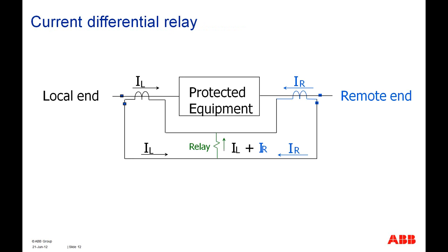So here we have this current differential diagram. As you can see, IL is the local current, and if the CT is connected with this dot notation, then if the current is flowing in this direction, the CT secondary current will be flowing in the other direction. IL is moving from here to here, and IR is the remote current direction. With this dot notation, IR is moving in this direction. The relay operating coil is in the differential path of these two circuits, and as you can see, IL plus IR will flow through the operating coil of this differential protection relay.